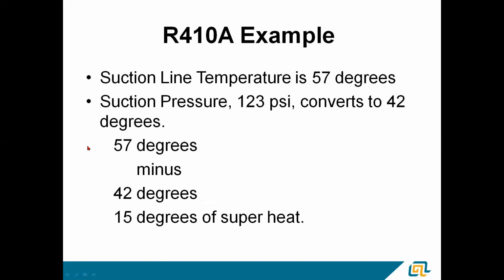Okay, so a quick R410A example. And like I say, I'm not going to get into this too deep because we've done this so many times over our career. Measure your suction line temperature. It's 57 degrees. And I look at my suction pressure. It's 123 PSI. Converts over to 42 degrees temperature-wise. If I do the math, 57 degrees for my suction line temperature, 42 degrees for my saturated suction temperature, come up with 15 degrees of superheat. That's kind of textbook. I think the next slide I got.